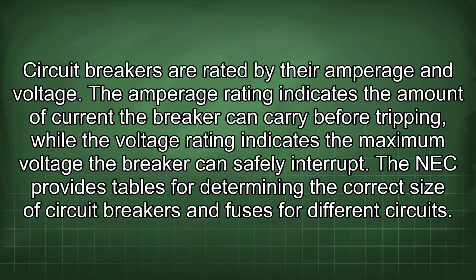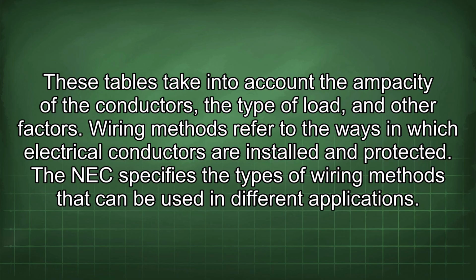The amperage rating indicates the amount of current the breaker can carry before tripping, while the voltage rating indicates the maximum voltage the breaker can safely interrupt. The NEC provides tables for determining the correct size of circuit breakers and fuses for different circuits. These tables take into account the ampacity of the conductors, the type of load, and other factors.